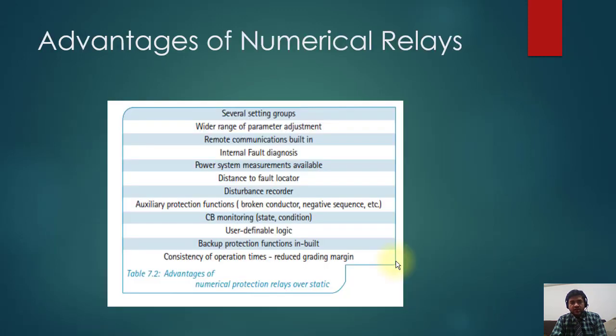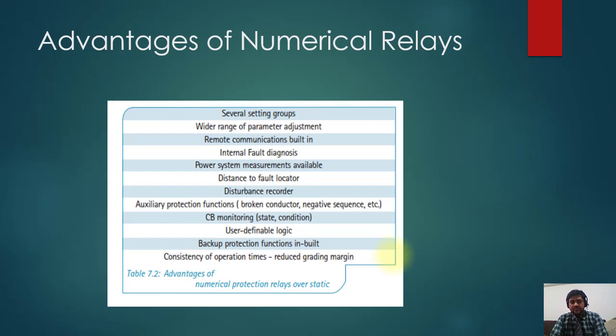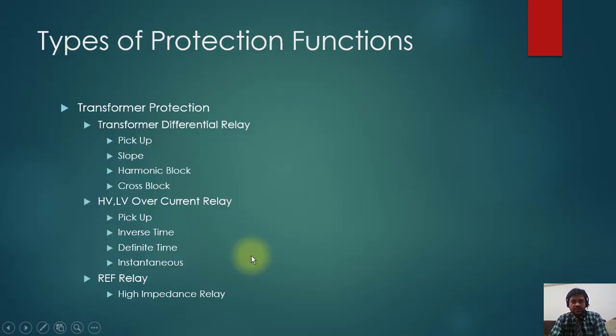Further advantages of numerical relays include several setting groups, a wider range of parameter adjustment, and remote communication capability because microprocessors are integrated — they have an interface for the latest automation systems. Numerical relays also have a built-in fault recorder, power system measurements always displayed, distance fault records, and a disturbance recorder. There are numerous functions and advantages.